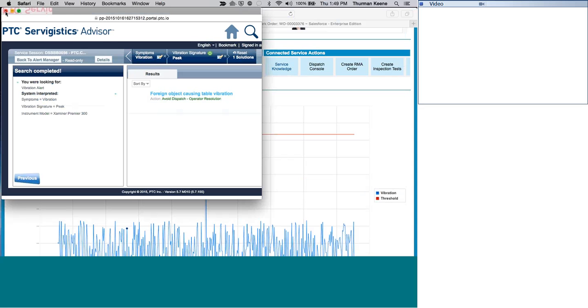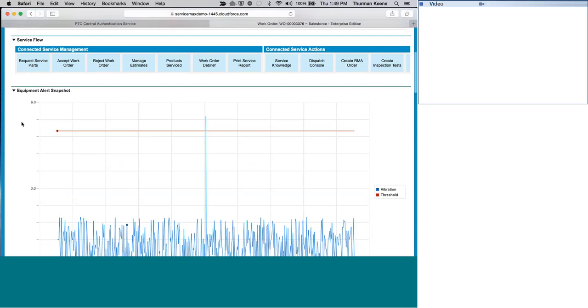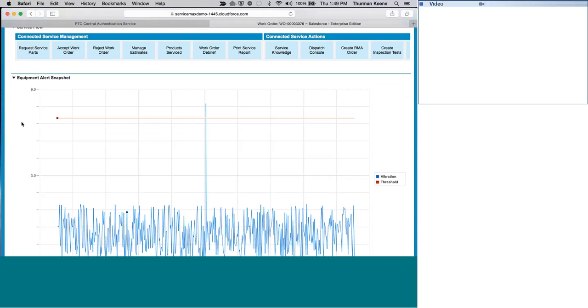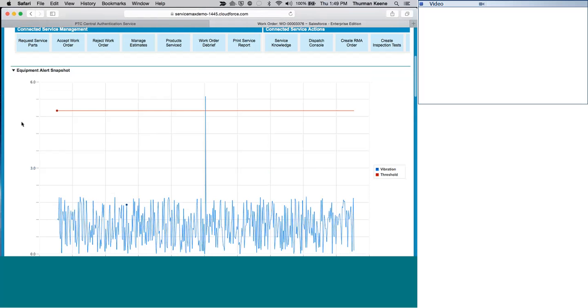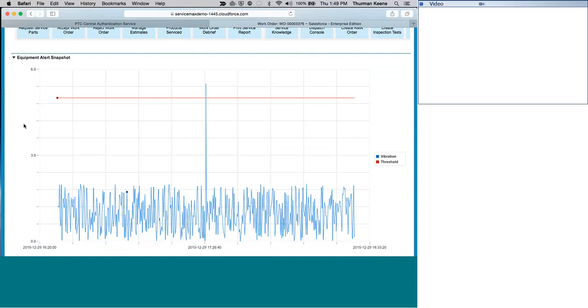If I close out of this and take a step back, I'm still that service engineer on the phone or looking at this remotely, and I see a snapshot of the problem. But there might be other areas I'm monitoring on this asset, this MRI machine, that could lead to this vibration. I have all kinds of sensors plugged into this MRI - vibration is just one of them. I might want to look at those other sensor readings to see if there are indicators of why this spike actually occurred.